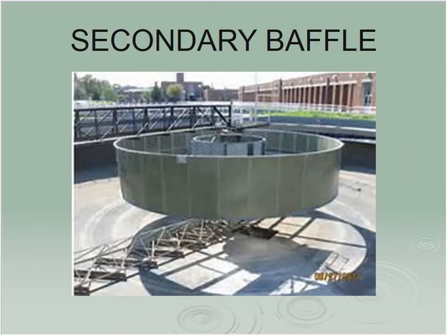There's another variation, the secondary baffle. This one's fairly high. Upper Blackstone has installed one that sits over the rake mechanism. It's probably not even a foot off the floor. So everything is going to come out of the feed well in the center, hit this baffle, and have to go over or under it. Again, just another means of holding it in the tank that much longer, close to its theoretical detention time.